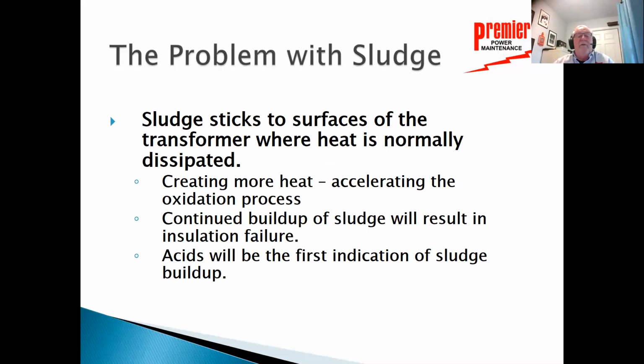Sludge sticks to the surfaces where the heat is normally dissipated. It creates more heat, accelerates the process of oxidation, and continues to build up more sludge, and you will actually end up with insulation failure. And with acids in the oil, one of the simple things we can do on an oil quality screen is look for the acids. That's one of the first indications of sludge buildup.